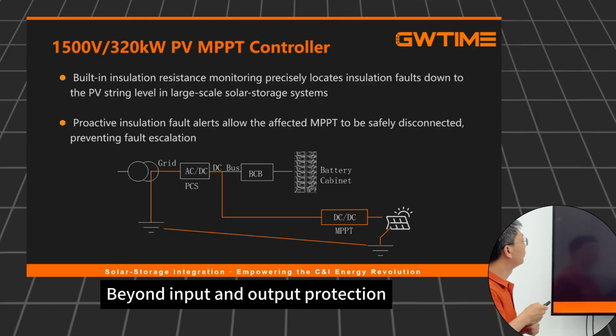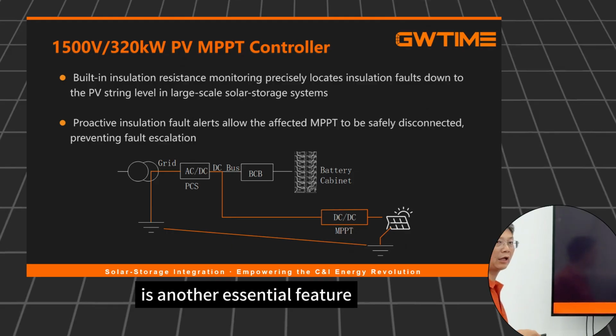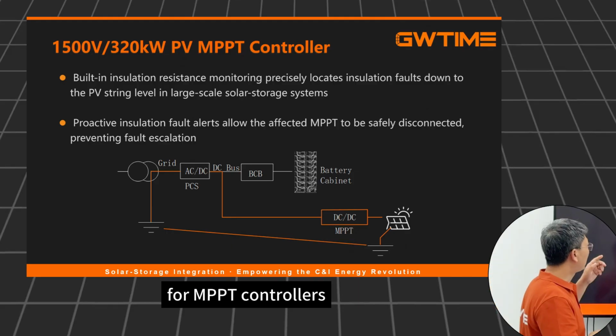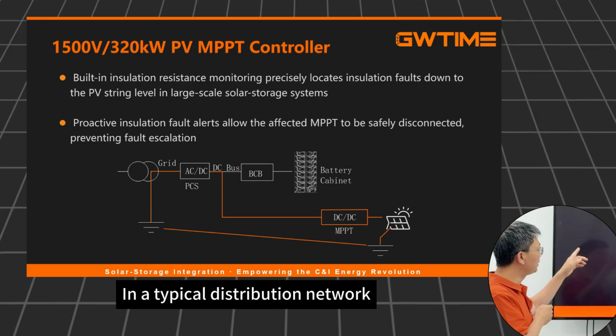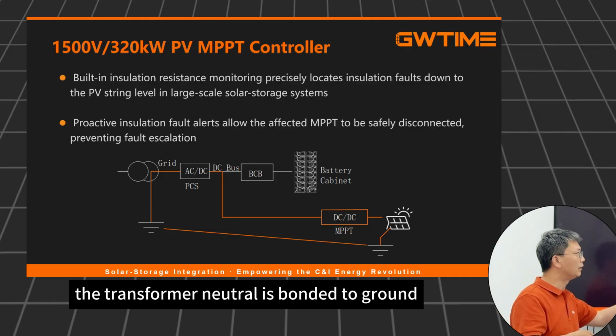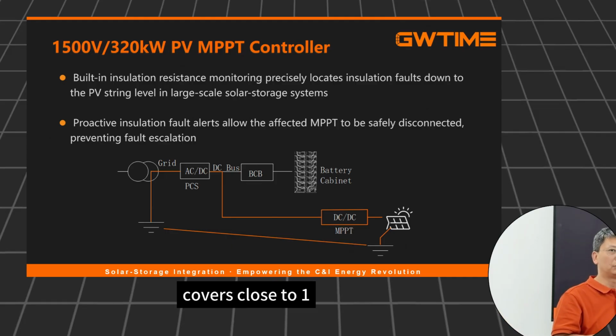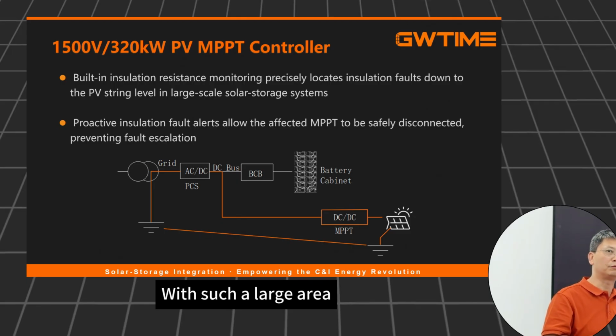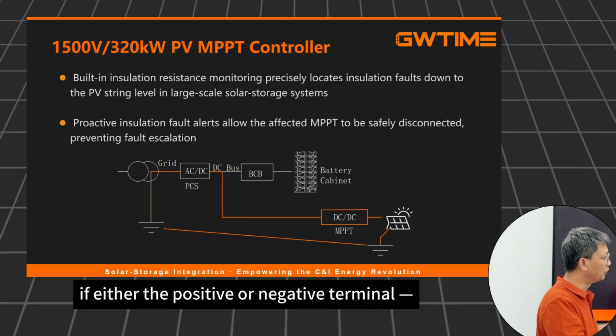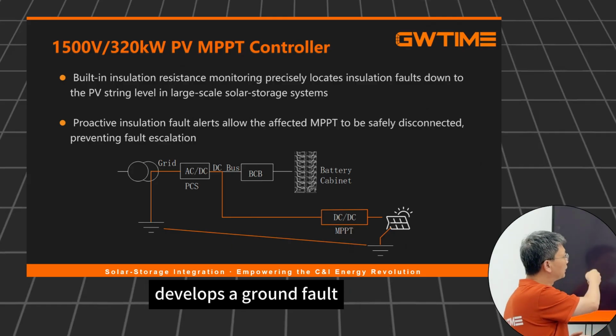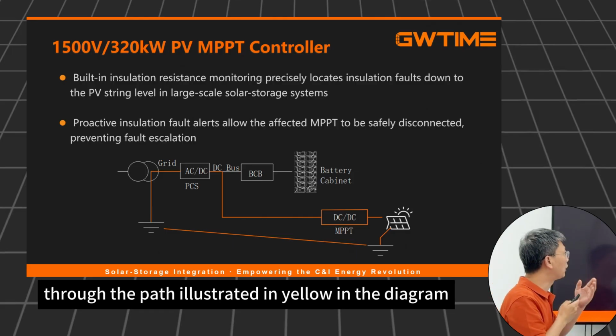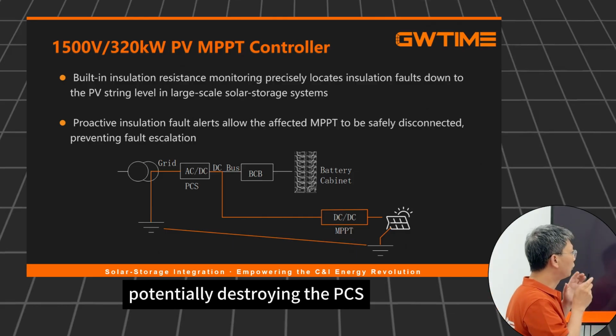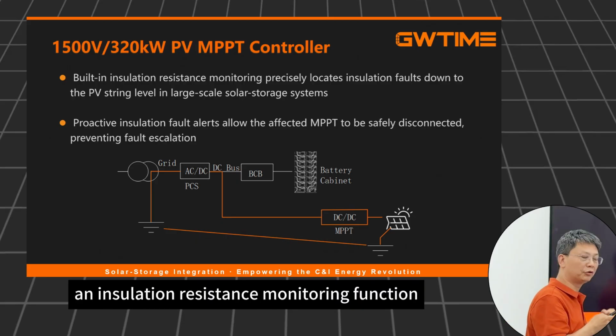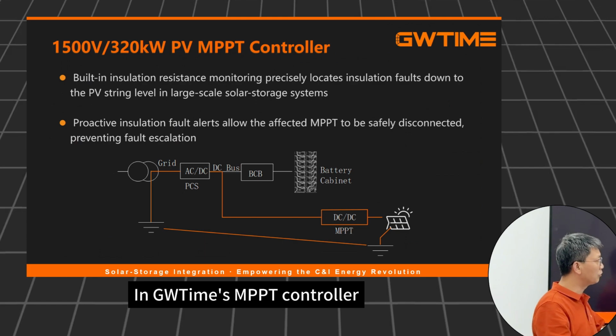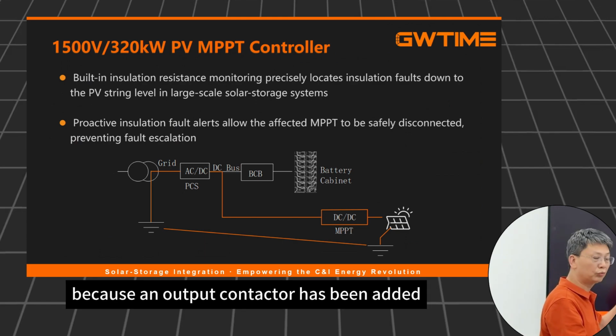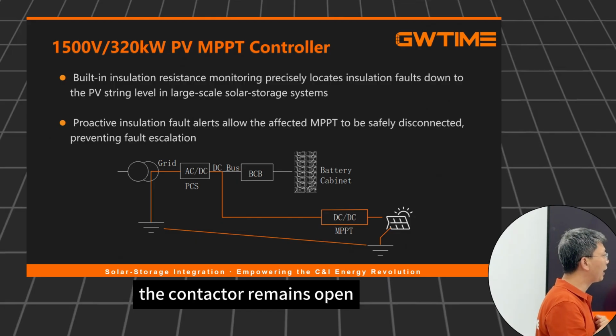Beyond input and output protection, insulation resistance monitoring is another essential feature for MPPT controllers. Why? In a typical distribution network, the transformer neutral is bonded to ground. A 100 kilowatt solar array covers close to 1,000 square meters. With such a large area, if either the positive or negative terminal or any intermediate stage develops a ground fault, a fault current will flow through the path illustrated in yellow in the diagram, potentially destroying the PCS. To prevent this, an insulation resistance monitoring function is essential. In GWTime's MPPT controller, because an output contactor has been added, the contactor remains open prior to each startup.